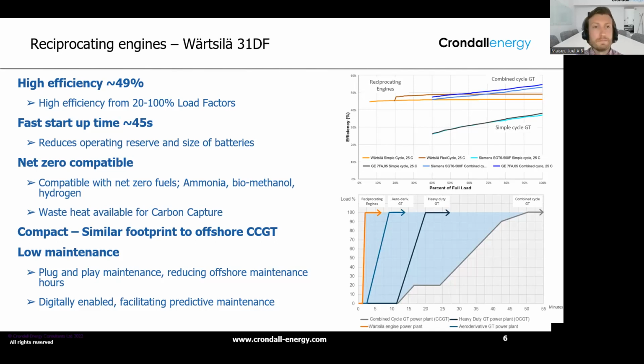The next reason we've selected reciprocating engines is their fast startup time. We're able to start up within 45 seconds, which, looking at the bottom right graph, is significantly faster than even the aeroderivative engines we're seeing offshore at the minute. That means we can minimize our spinning reserve, so rather than having engines sat there running and emitting without providing power to the grid, we can use energy storage and shrink the size of that storage thanks to these batteries.